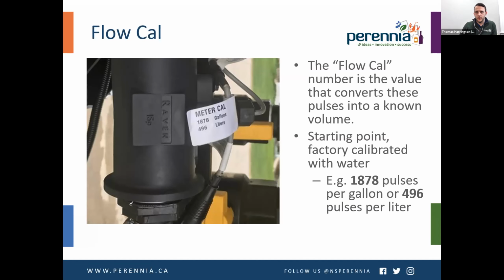So this flow cal number is the value that actually converts these pulses into a known volume. And these are factory calibrated with water. For example, this flow meter has a cal number of 1,878 pulses per gallon, or 496 pulses per liter. So when you get your rate controller set up, that's going to give you a really good starting point for calibrating your flow meter.